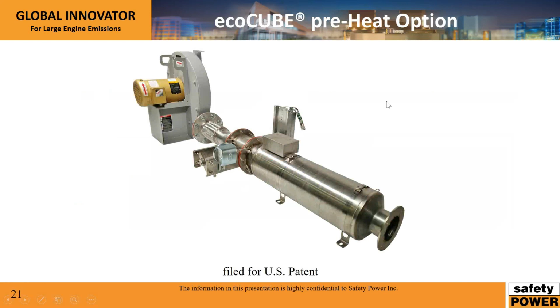As a side note, I'll mention our electric preheat system. This might not be necessarily relevant to greenhouse applications, but it might be in certain cases. Typically these are used for installations where an air permit is required. Because of the large thermal mass of the SCR catalyst, there's a certain heat-up time, and the chemical reaction is only activated above 300 degrees Celsius. That heat-up time, depending on system size, can be 30 minutes or sometimes more, which for air permits a lot of the time is not acceptable.